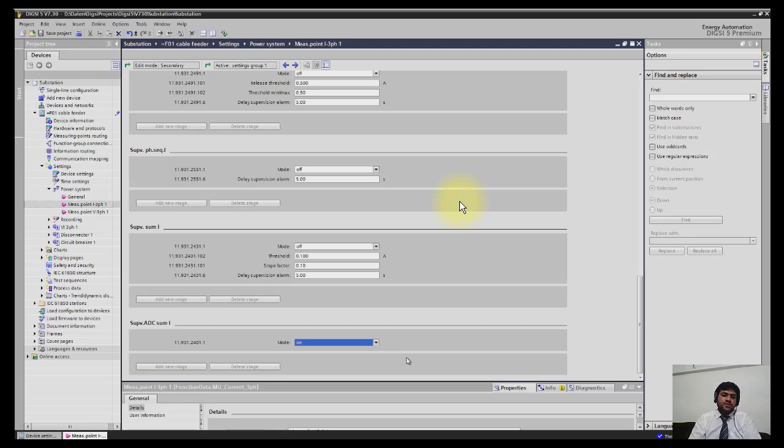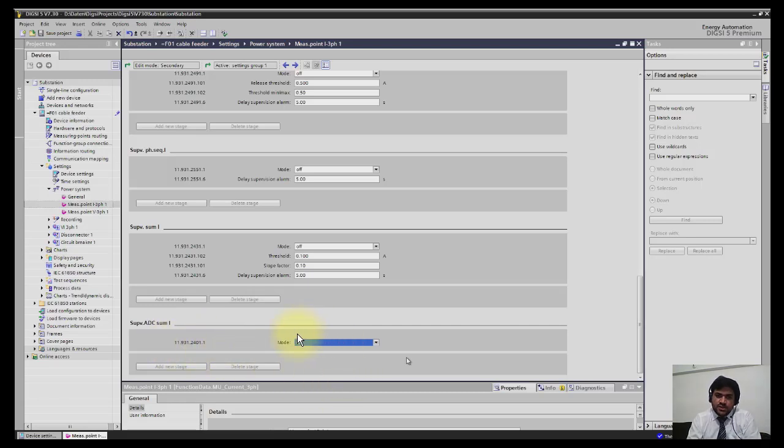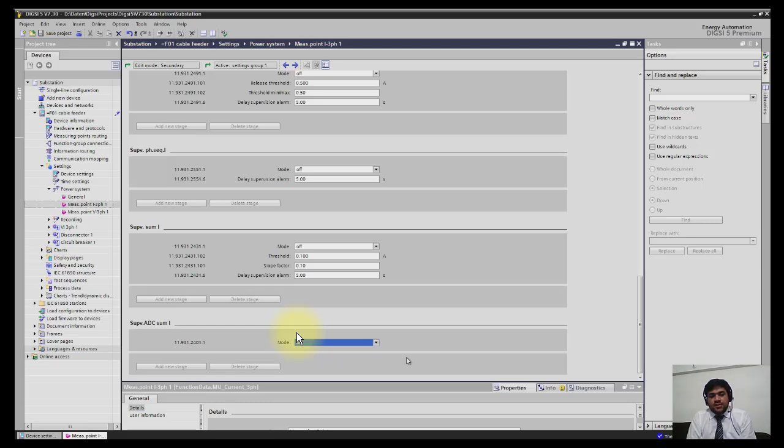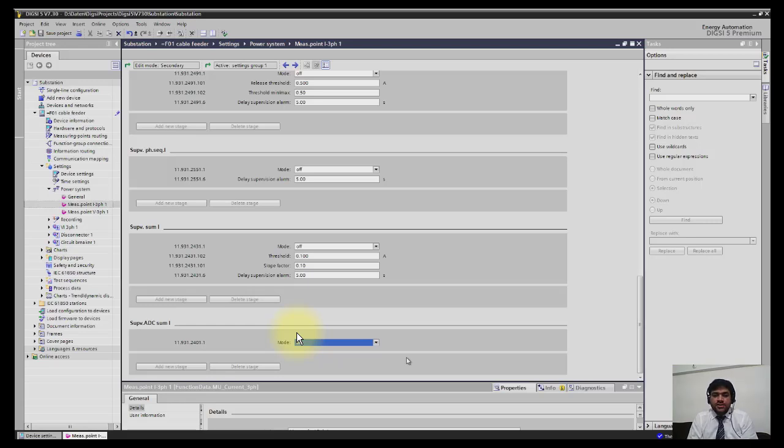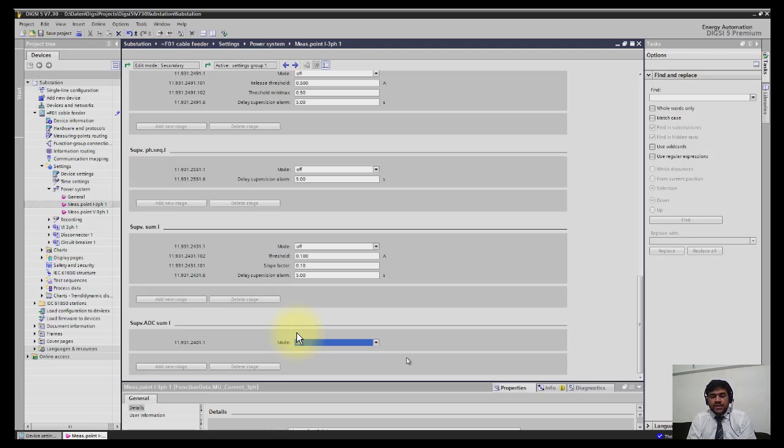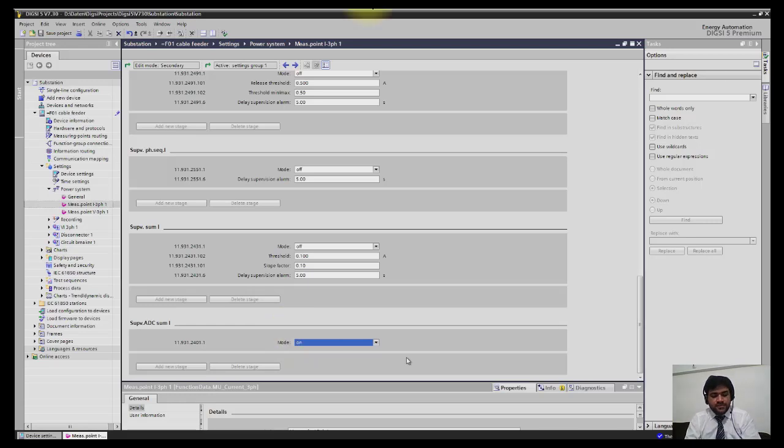There's another excellent function added in DIGSI 5 which was not in DIGSI 4: supervision of ADC, analog-to-digital converters. Each analog input has two converters and these converters are cross-checking each other's outputs. It checks the sum of three currents with the neutral current, and if the difference is greater than the threshold, it will block the protection function fed through this current element, helping to prevent malfunction of the relay.